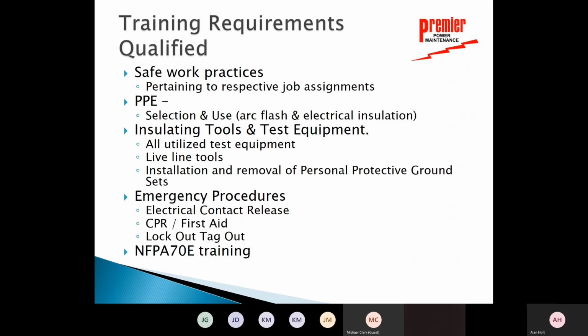Now, they say that safe work practices, basically, you've got to be trained in and familiar with all the electrical safety related work practices that are required by this policy and by Premier's policy and by the particular job that you're doing. You need to be trained on personal protective equipment. That includes selecting the proper arc flash clothing, the rating of the shirts, the pants that you've got on, the proper hard hats, the proper gloves, all those sorts of situations, any kind of shielding material, any other personal protective equipment. You need to be trained on that. When it comes to insulating tools, you need to be knowledgeable of each piece of test equipment in its use and in its ratings. So basically, this kind of supports what MSHA tells us to do.